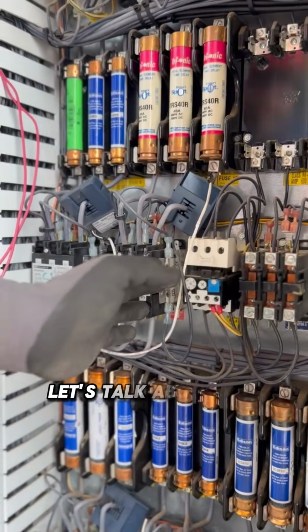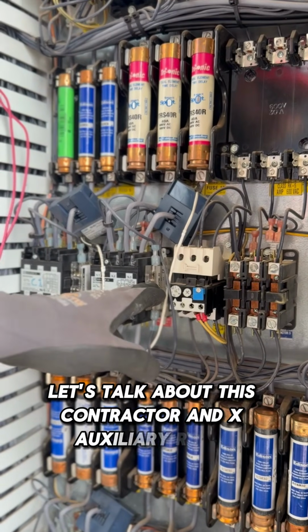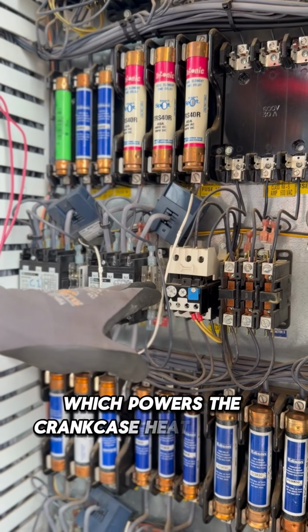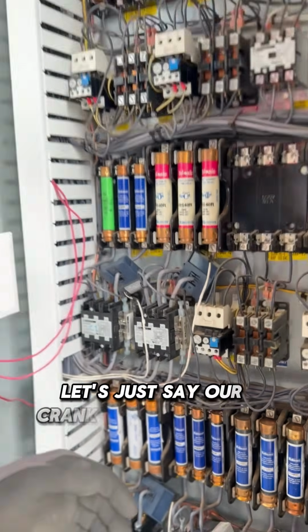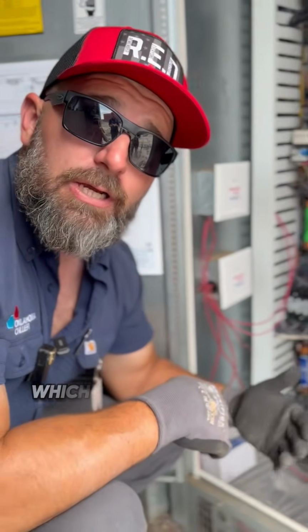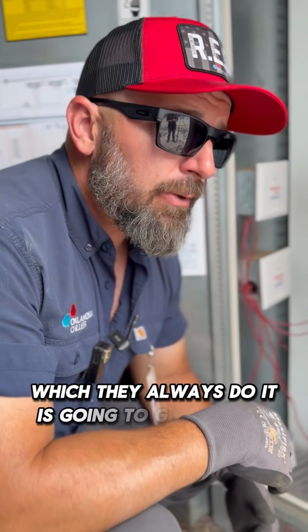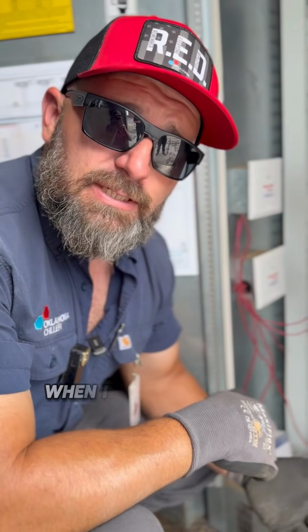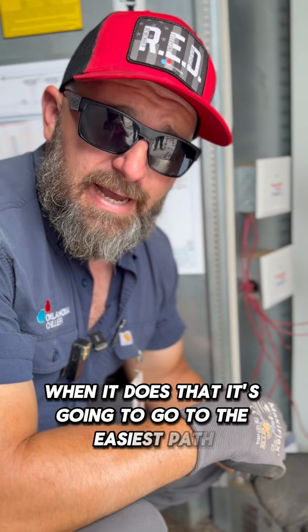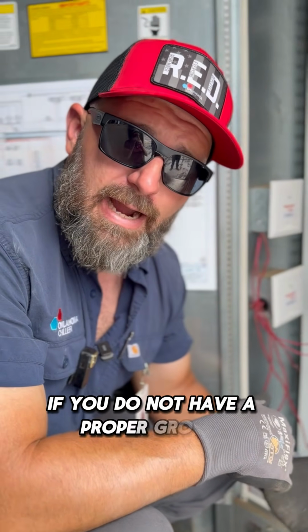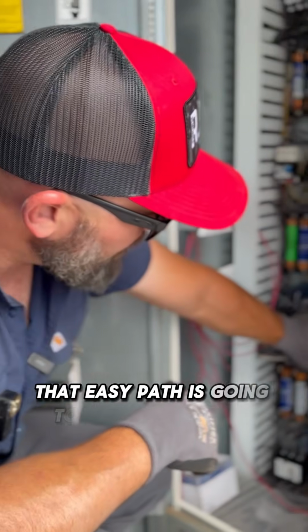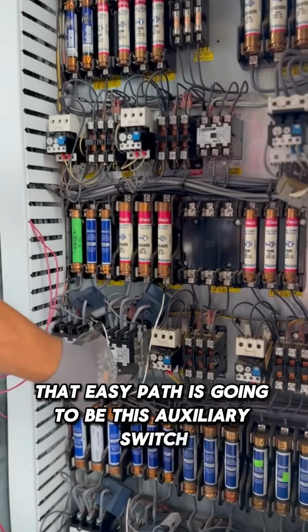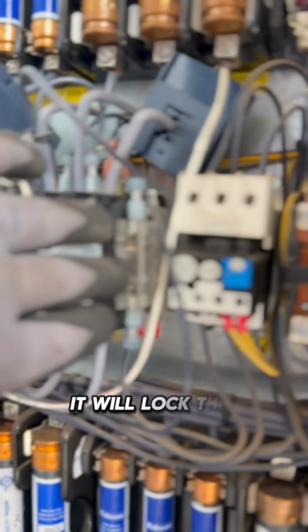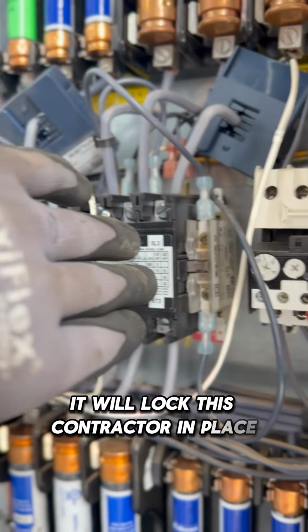So let's talk about this contactor and its auxiliary relay which powers the crankcase heater strips. Let's just say our crankcase heater strip fails, which they always do. It is going to go short to ground. And when it does that, it's going to go to the easiest path. If you do not have a proper ground, that easy path is going to be this auxiliary switch. When this auxiliary relay fries, it will lock this contactor in place.